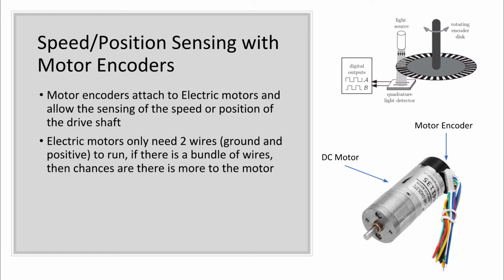With motor encoders, there are 2 different types: relative and absolute. The relative is essentially a light source and a detector, with a disc that has slits in it, and as it spins, this light is interrupted. So the faster it spins, the more frequently that light beam is interrupted, and you can measure that.